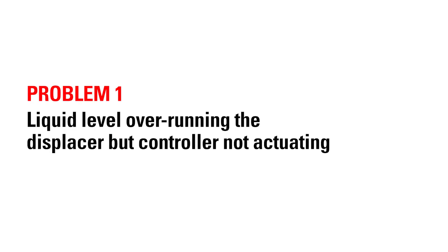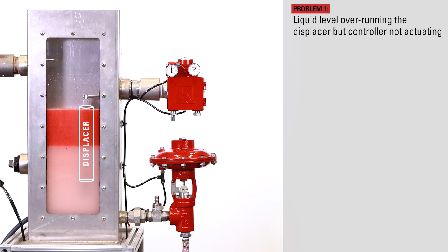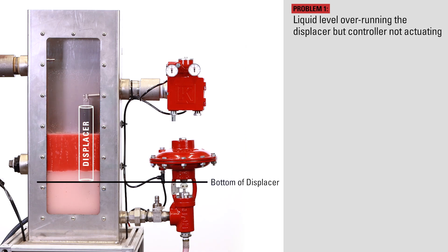When the liquid level reaches its set point, either at the top of the span or the bottom of the span, the controller should actuate, meaning it sends an output signal or vent. The controller should actuate somewhere along the length of the displacer. If the liquid level goes beyond the top of the displacer but the controller hasn't actuated, or if the liquid level drops below the bottom of the displacer and the controller hasn't actuated, this is a problem.